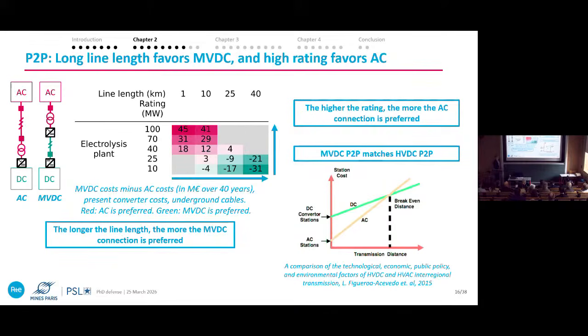This is an example of a paper where you can compute the transmission cost depending on distance. If you have low distance, AC is preferred; high distance, DC is preferred. Also, if you have high rating, the gap between DC converter station cost and AC station cost increases, so the cost break-even distance becomes higher.